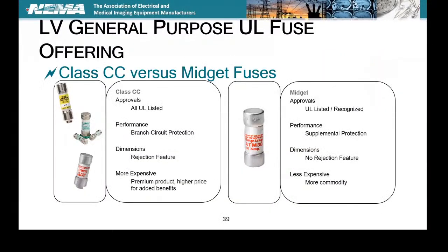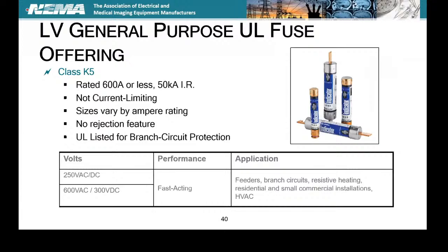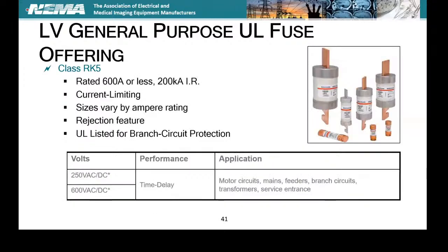So your Charlie Chaplins, we call them Charlie Chaplins because of that little dimple on the top. Your CC fuses, your K5. Now you've got fuses that are not current limiting. The interrupting rating is much less: up to 50,000 amps on a 600 volt, or up to 600 amps. There's no rejection features for these. The rejection features come into play whenever you want to make sure you don't put one of these inside of a switch that is meant to have current limiting devices. They come in 250, 600, and 300 volt DC. Feeders, branch circuits. You'll see a lot of these on HVAC. They're low cost, non-current limiting devices.